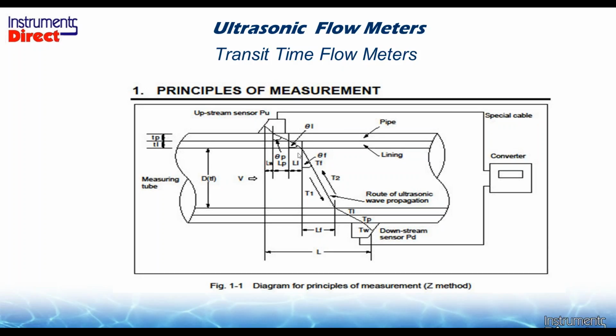And then when it hits the liquid, a phenomenon occurs. It's called Snell's law. You ever put a straw in a glass of water and look at it sideways? It kind of looks like it's chopped in half there. Well, it refracts the sound at a specific angle, and we need to know the angle. We need to know the sound speed of the liquid going through, and then we reverse that with the same calculations, and that's a lot of math.